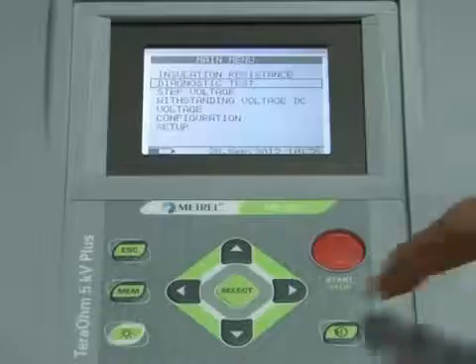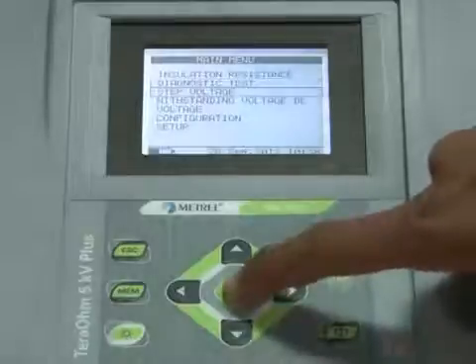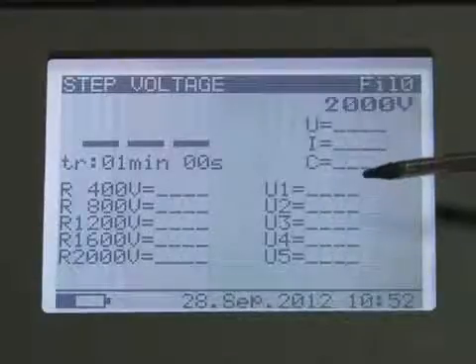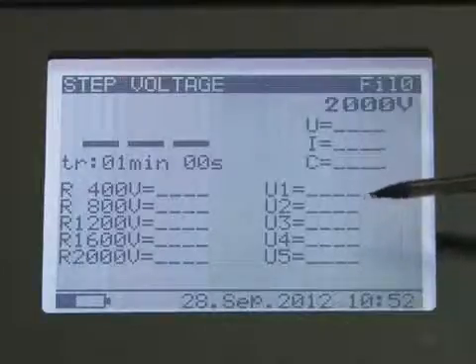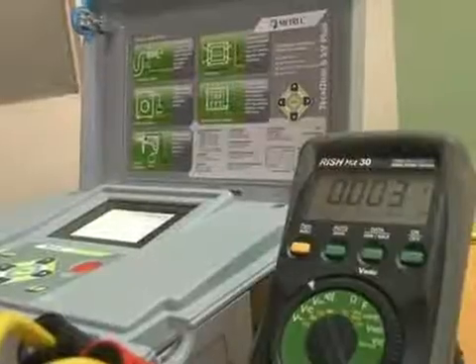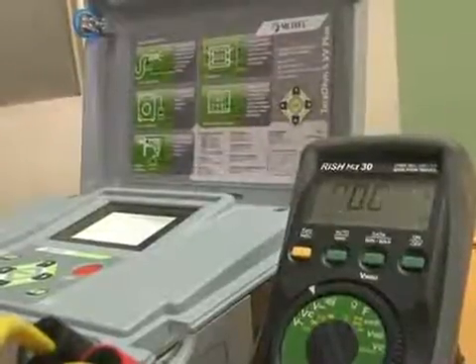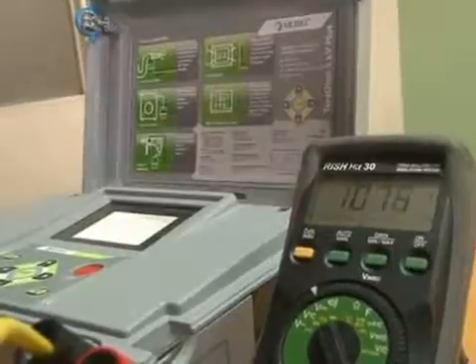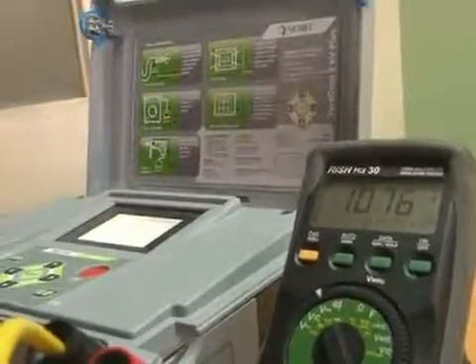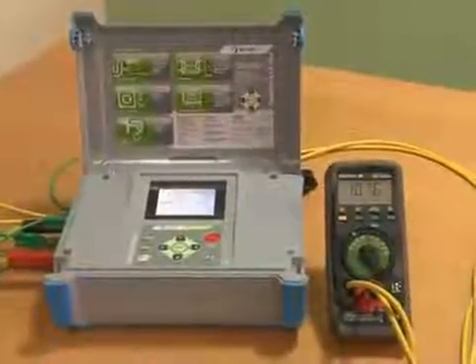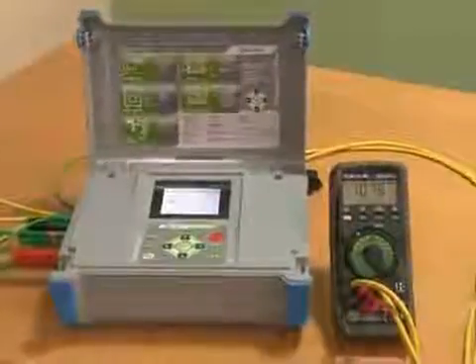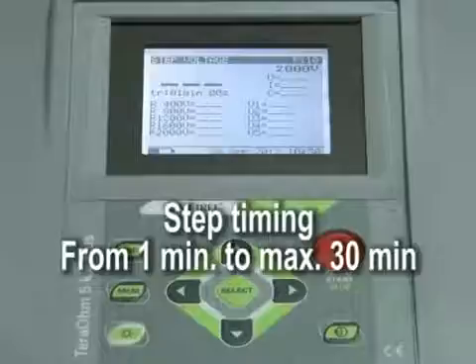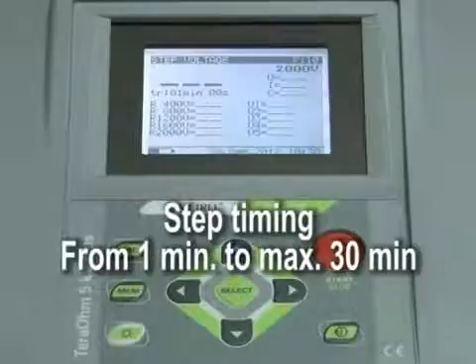For step voltage insulation resistance testing, after selecting the step voltage menu, the user gets a screen showing the initial state without readings. After connecting the test leads, the user can start the measurement. The user can define the step voltage, step time, and select graphical or numerical mode. Step timing can be defined from 1 minute to a maximum of 30 minutes.